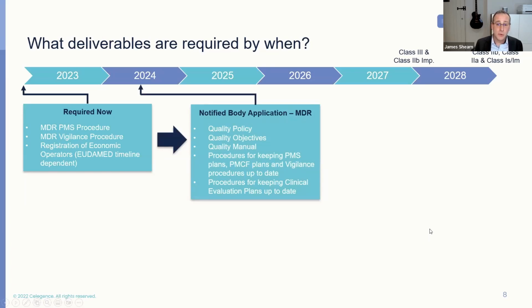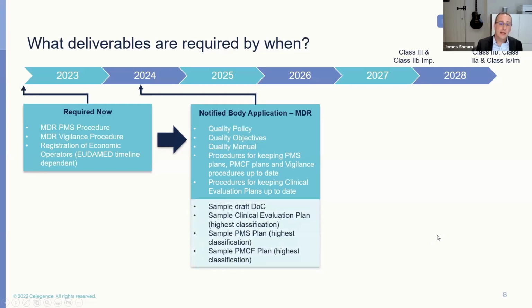No later than May of 2024, to make the application to a notified body for MDR assessment, that will require manufacturers to submit to the notified body quality policy, quality objectives, a quality manual that has been updated to the requirements of MDR, and also MDR compliant processes for keeping post-market surveillance plans, post-market clinical follow-up plans, vigilance procedures, etc. up to date, and also procedures for keeping up-to-date clinical evaluation plans. In addition, manufacturers also have to submit a sample declaration of conformity to MDR and a sample clinical evaluation plan, sample post-market surveillance plan, and sample post-market clinical follow-up plan, each for the highest classification device that will go under any given certificate. So an awful lot of work has to be completed under the QMS and to certain deliverables in order to actually facilitate the act of doing a submission for assessment to a notified body and having that submission accepted.